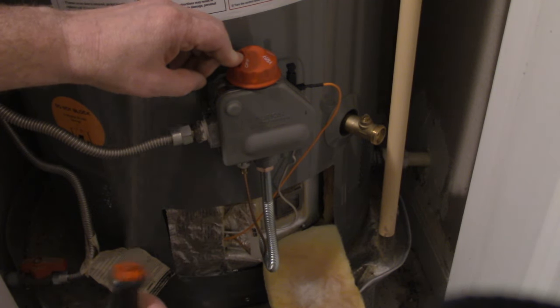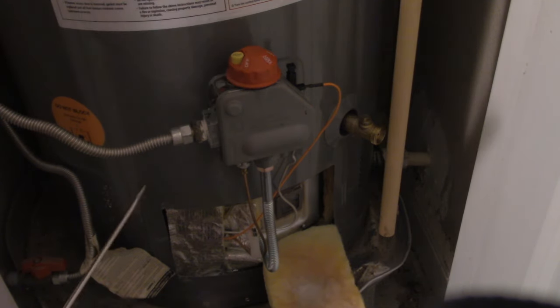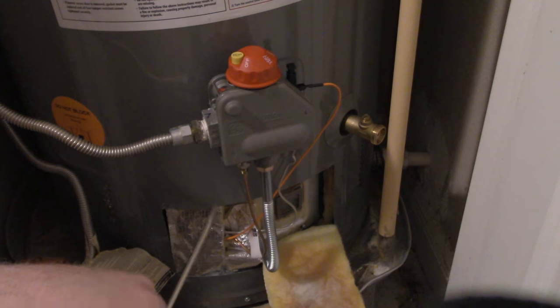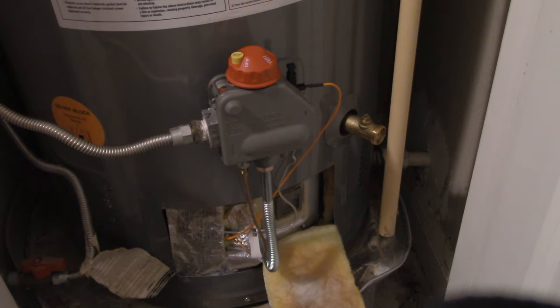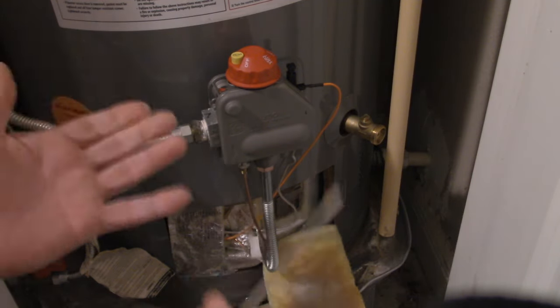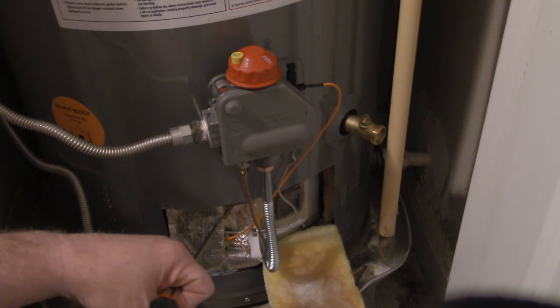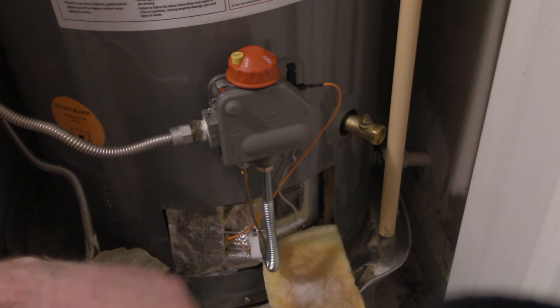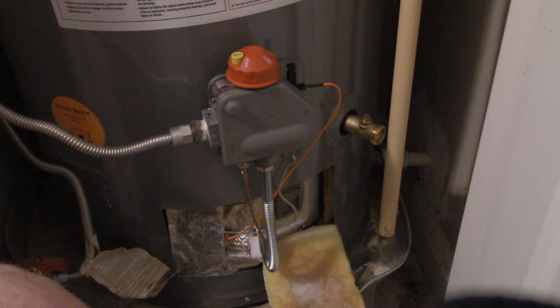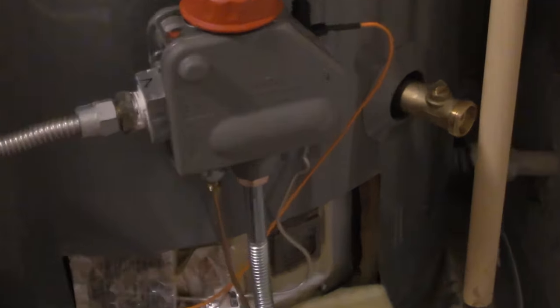So the problem is, if this thermocouple loses that voltage, for whatever reason, it shuts this off and when you lift the pilot light up, that flame will extinguish. The theory with that is, if your pilot light blows out, you don't want to fill your closet, your house, with the propane or the natural gas that should be going to that pilot light. So how do we fix that?